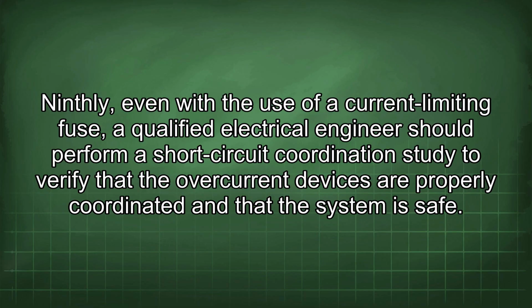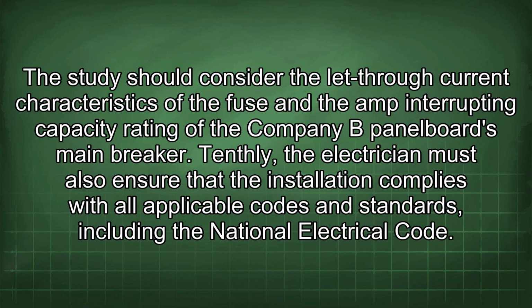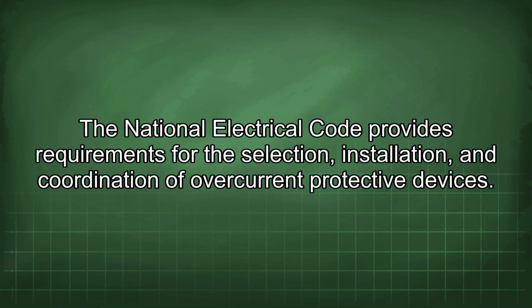Ninthly, even with the use of a current limiting fuse, a qualified electrical engineer should perform a short-circuit coordination study to verify that the overcurrent devices are properly coordinated and that the system is safe. The study should consider the let-through current characteristics of the fuse and the amp interrupting capacity rating of the company B panel board's main breaker. Tenthly, the electrician must also ensure that the installation complies with all applicable codes and standards, including the National Electrical Code. The National Electrical Code provides requirements for the selection, installation, and coordination of overcurrent protective devices.